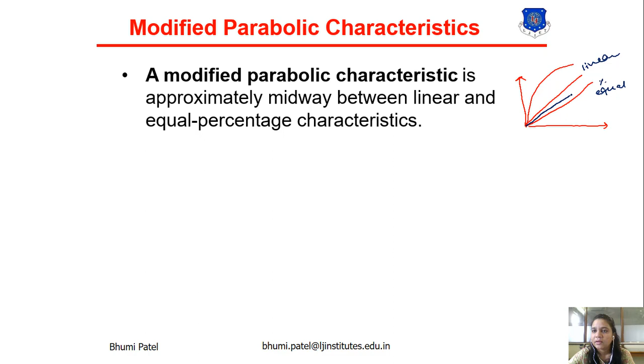Okay, so what is the modified parabolic? It is midway between the linear and equal percentage. So this is the linear characteristic and this is the equal percentage. Between these, it is known as the modified parabolic characteristic. It provides fine throttling at the low flow capacity and approximately linear characteristic at the high flow capacity.